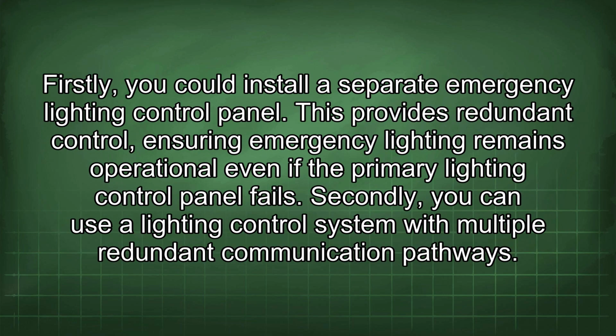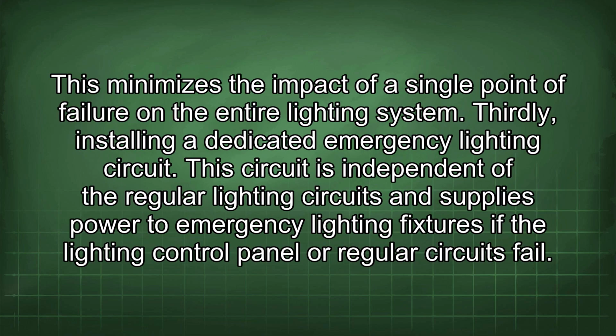Firstly, you could install a separate emergency lighting control panel. This provides redundant control, ensuring emergency lighting remains operational even if the primary lighting control panel fails. Secondly, you can use a lighting control system with multiple redundant communication pathways. This minimizes the impact of a single point of failure on the entire lighting system.